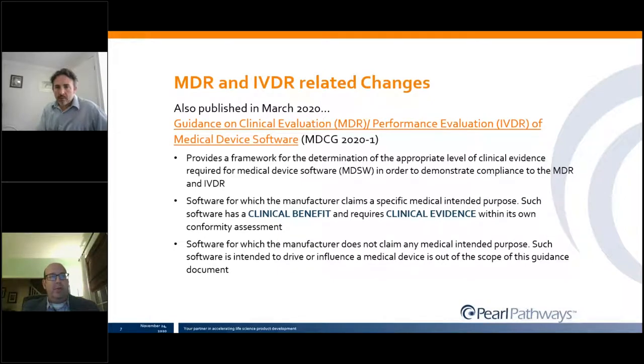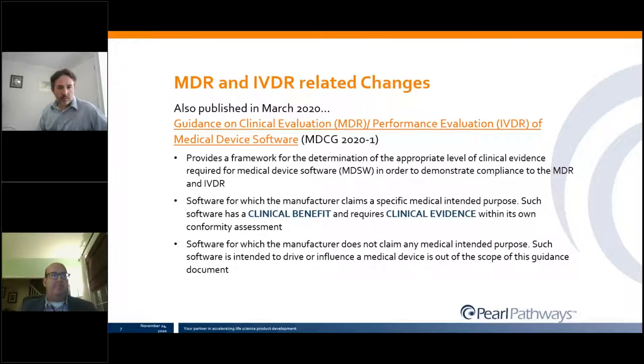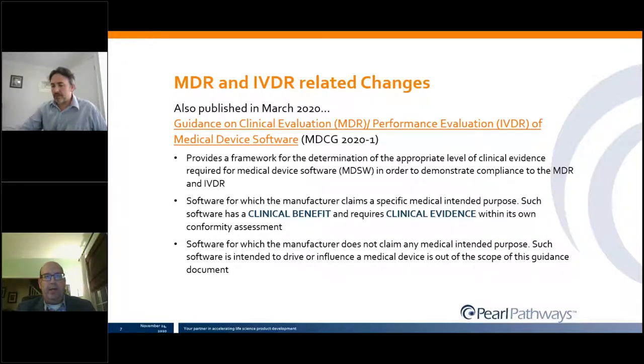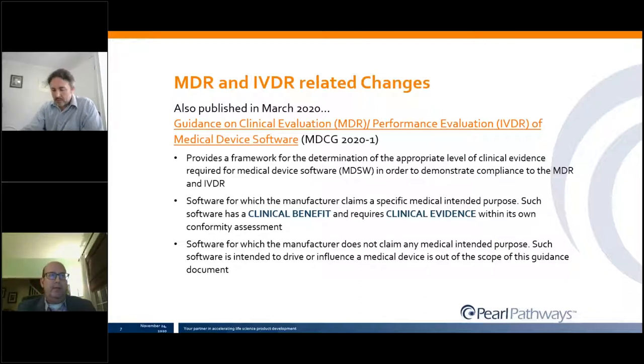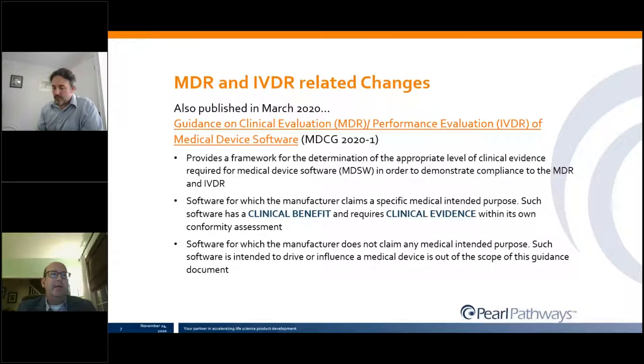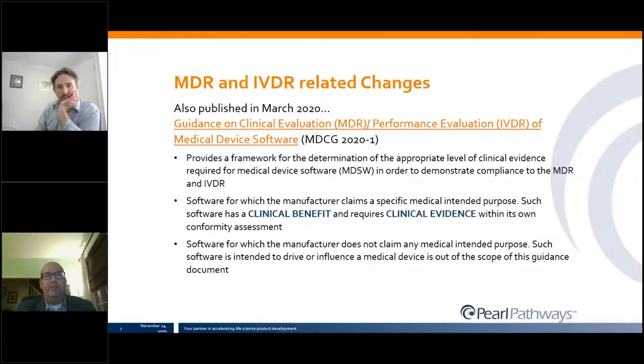Also published in March 2020 was MDCG 2020-1, a guidance on clinical evaluation and performance evaluation requirements for medical device software. This guidance provides a framework for determining the appropriate level of clinical evidence needed for medical device software to demonstrate compliance with MDR and IVDR requirements. If the software has a clinical benefit, clinical evidence is required to demonstrate conformity. Software for which the manufacturer does not claim medical intent is outside the scope of this guidance — it is really about medical device software.